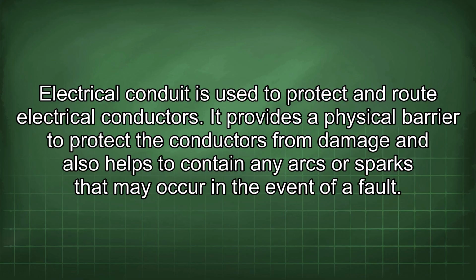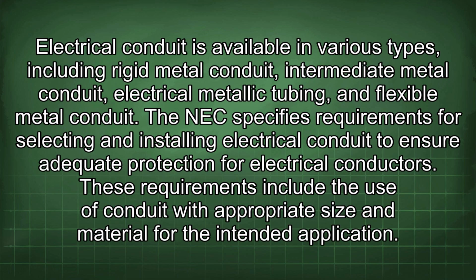It provides a physical barrier to protect the conductors from damage and also helps to contain any arcs or sparks that may occur in the event of a fault. Electrical conduit is available in various types, including rigid metal conduit, intermediate metal conduit, electrical metallic tubing, and flexible metal conduit. The NEC specifies requirements for selecting and installing electrical conduit to ensure adequate protection for electrical conductors. These requirements include the use of conduit with appropriate size and material for the intended application.